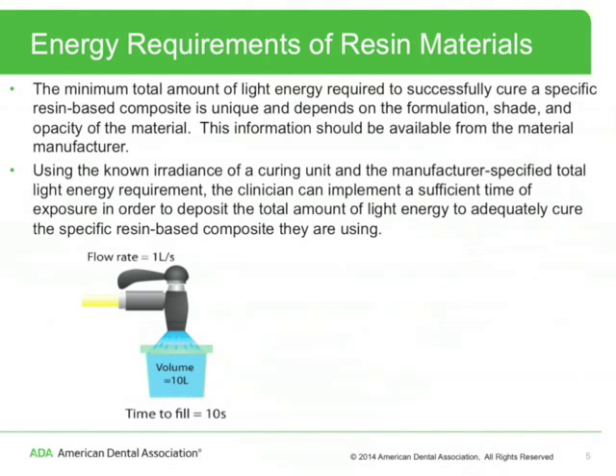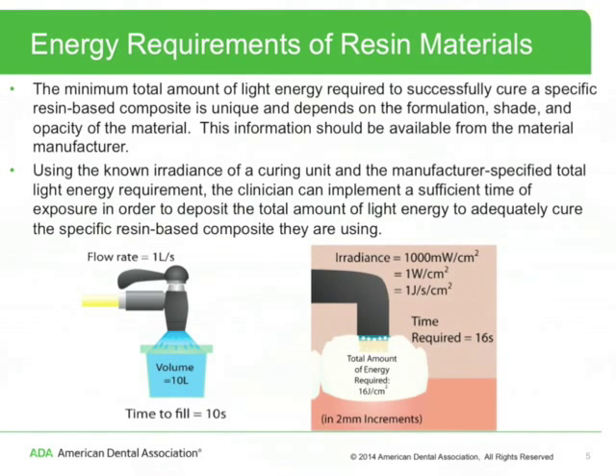Using the hose and bucket analogy, if water flows from the nozzle at one liter per second and the bucket volume is 10 liters, it will take 10 seconds to fill the bucket. Similarly, if the irradiance of a curing unit is 1,000 milliwatts per square centimeter — which is the same as 1 joule per second per square centimeter — and the minimum total light energy required to adequately cure the restorative material is 16 joules per square centimeter, then to adequately cure a 2 millimeter thick increment it takes a minimum of 16 seconds.